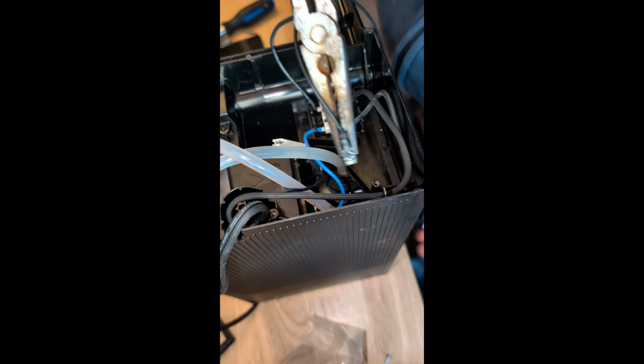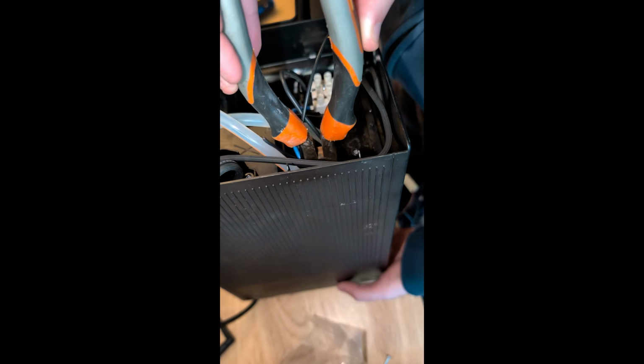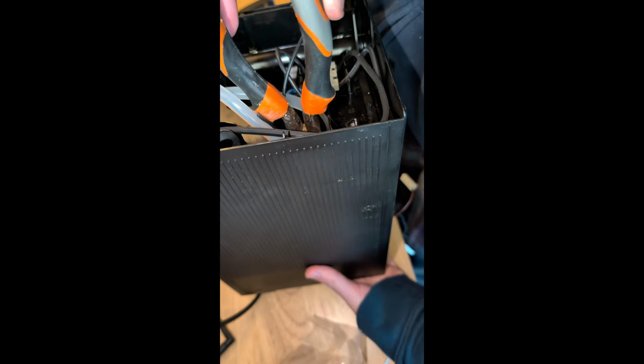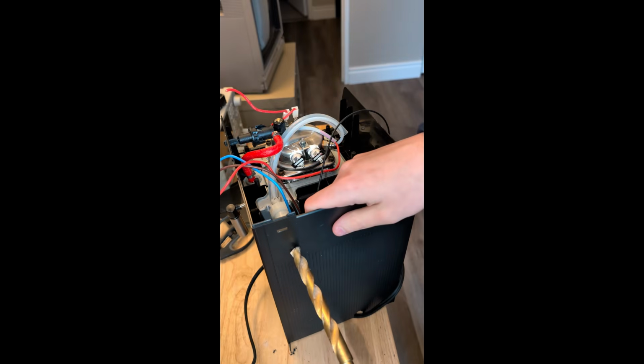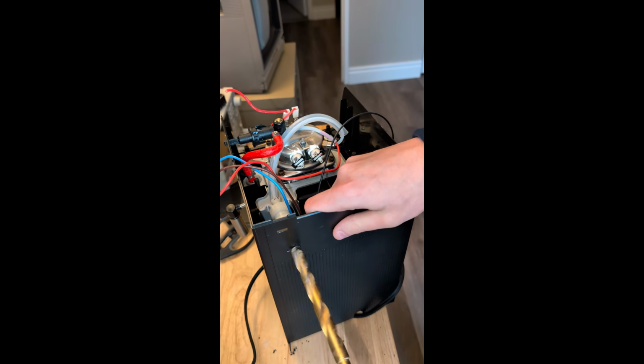Using needle nose pliers, it's time to reinsert the piggyback connector into the pump. Make sure you hold the bottom of the pump while you do this. It's now time to drill a hole in the back of the machine where all of our cables will eventually go into the backpack. I recommend a 1/2 inch hole here.